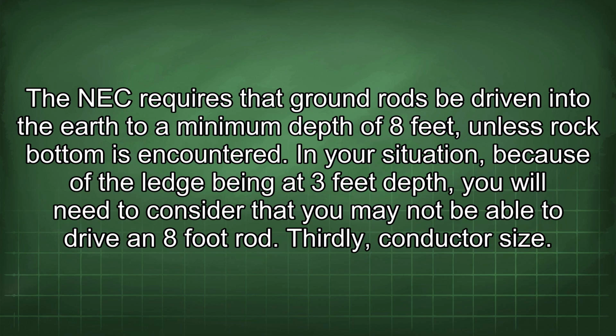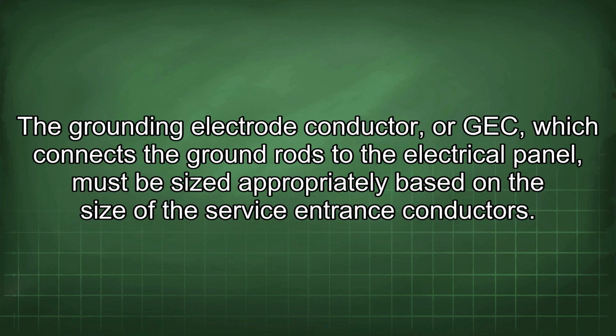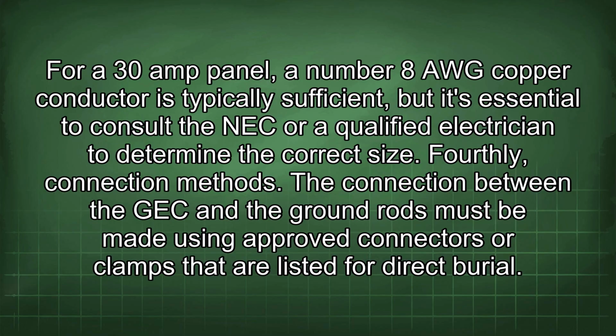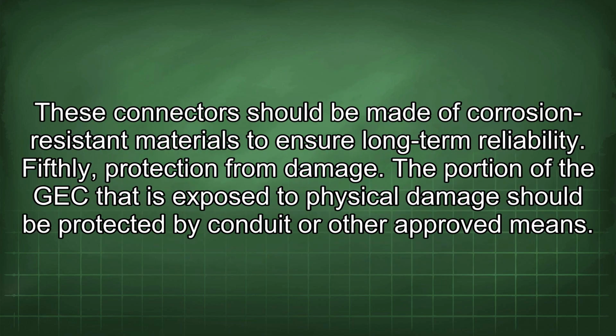Thirdly, conductor size. The grounding electrode conductor, or GEC, which connects the ground rods to the electrical panel, must be sized appropriately based on the size of the service entrance conductors. For a 30 amp panel, a number 8 AWG copper conductor is typically sufficient, but it's essential to consult the NEC or a qualified electrician to determine the correct size. Fourthly, connection methods. The connection between the GEC and the ground rods must be made using approved connectors or clamps that are listed for direct burial. These connectors should be made of corrosion-resistant materials to ensure long-term reliability.